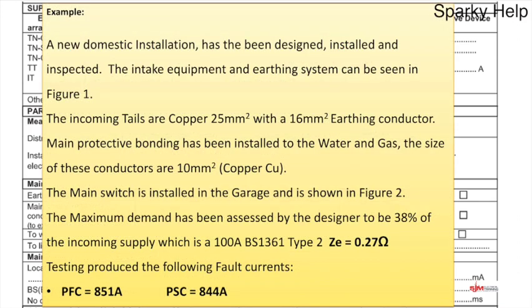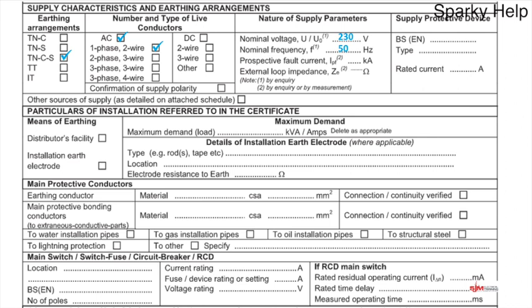So let's look at our details that we had, and right down the very bottom it says PFC, the testing procedures for fault currents. PFC is 851 amps and the PSC is 844. So which of these two are we after? Well, actually we're only after the largest value, so it's 851 is what we're after. These are the values being given in kA, so we're going to put 0.851 kiloamps. Next one down, external earth fault loop impedance.